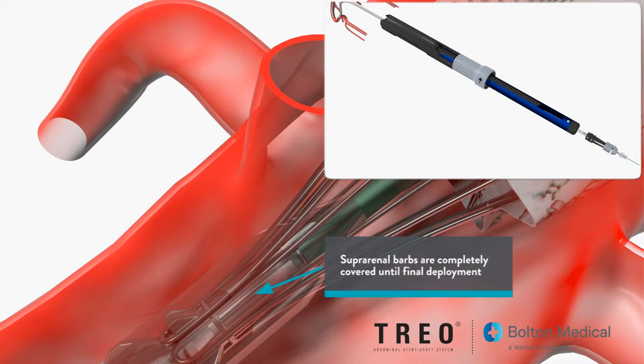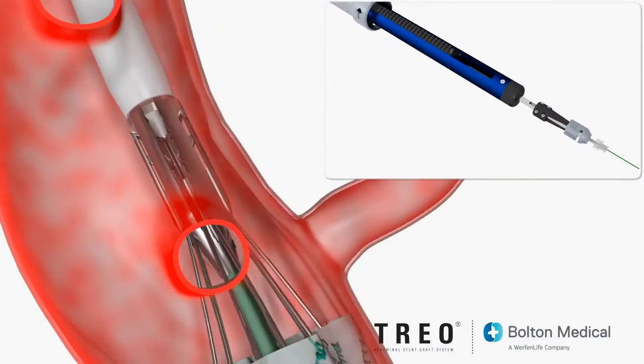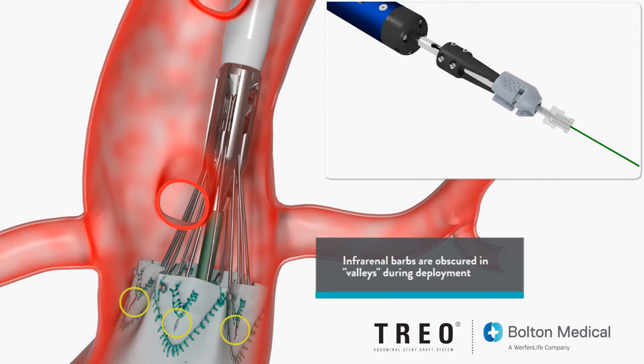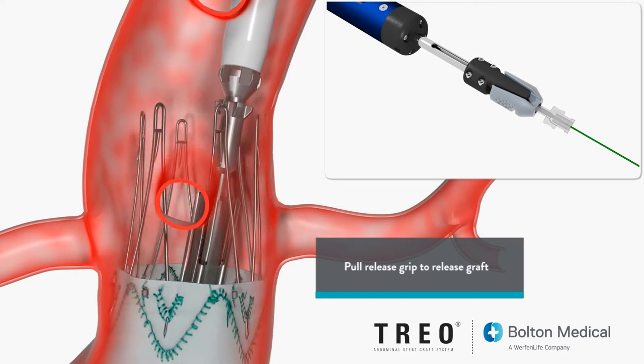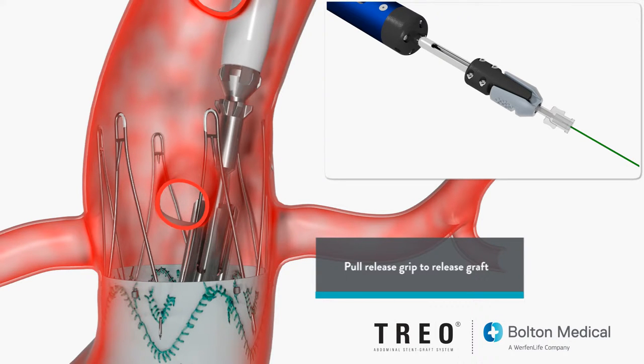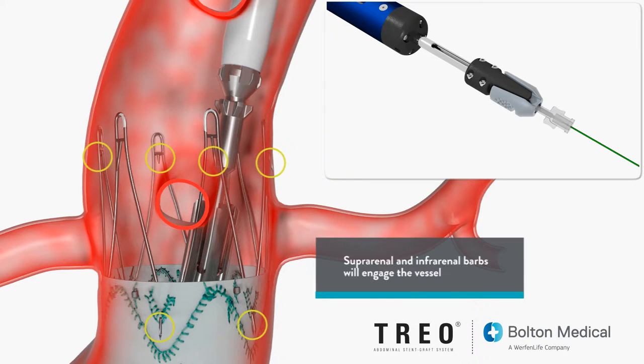The suprarenal barbs are completely covered and the infrarenal barbs are substantially obscured in valleys created by the proximal stent. To release the proximal clasp, first push the gray knob cranially and turn it to release the black release grip. While observing the proximal clasp assembly under fluoroscopy, pull the release grip caudally until it clicks twice to release the bare stent. At this point, the suprarenal and infrarenal barbs will engage the vessel.